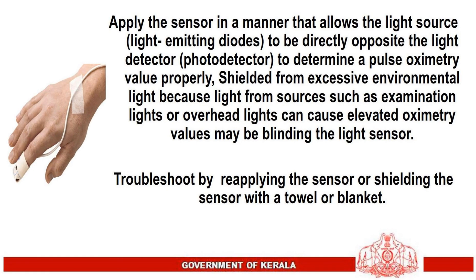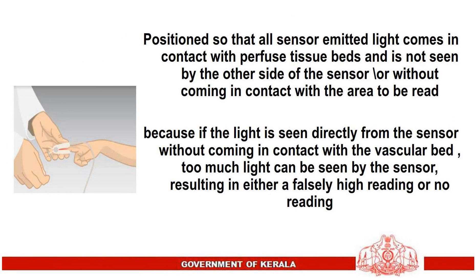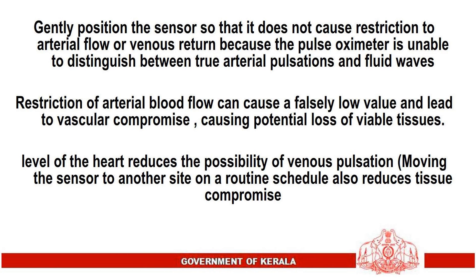Apply the sensor so that the light emitting diodes are directly opposite the photo detector, and properly shielded from excessive environmental light. Light from examination lights or overhead lights can cause elevated oximetry values by blinding the light sensor — troubleshoot by reapplying the sensor or shielding it with a towel or blanket. Position so that all sensor-emitted light comes in contact with perfused tissue beds. If light is seen directly from the sensor without contact with the vascular bed, too much light can reach the sensor, resulting in a falsely high reading or no reading.